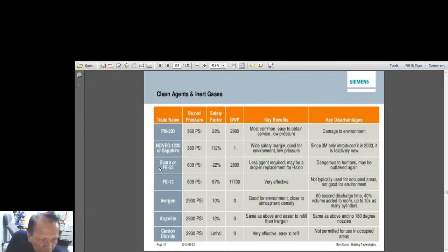ECAR or FE25, 609 psi, so very high. Minus 22% factor, 2,800 for GWP. Less agent required, maybe a drop-in replacement of halon. So it says it is a possible replacement. Then dangerous to humans, maybe outlawed again. Oh my God! So this is an X. So dangerous to humans. Okay, let's go to FE13.